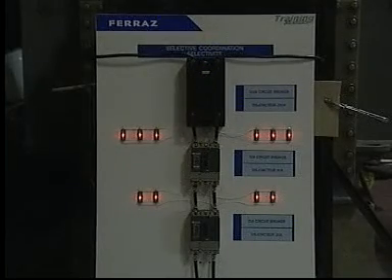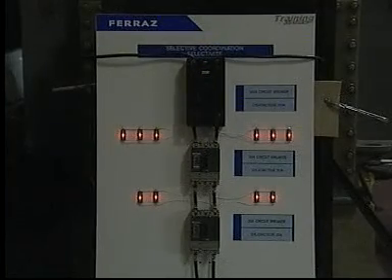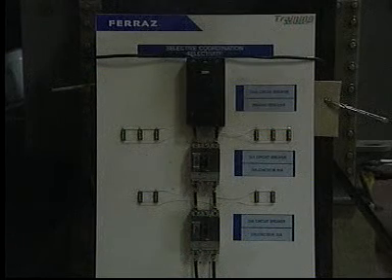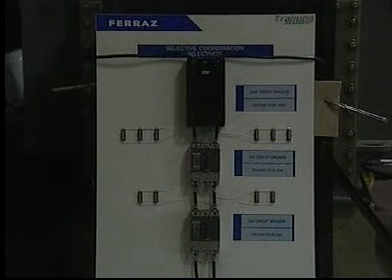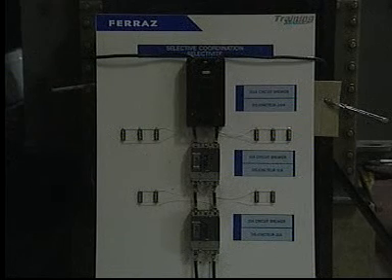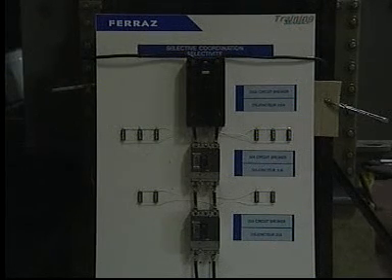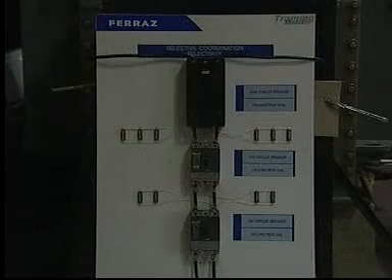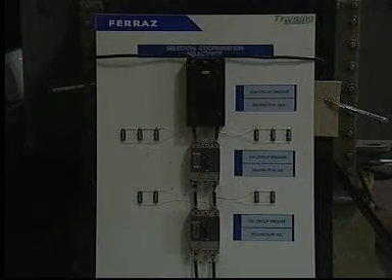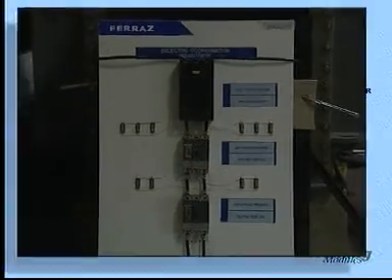The lights represent the main and feeder circuits, with the closing switch creating a fault on the branch circuit. The result is that all three breakers open, causing a total system blackout. This could be predicted, since the fault current of 15,000 amperes is well above the 2,000 ampere instantaneous trip of the main 200 ampere breaker.